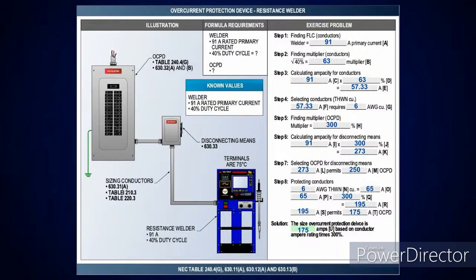So now I've already said, based on 630.32(A), I can take it at 300%. So I'll take the 91 amps for the welder at 300%, which gives me 273 amps. It says that the rating or setting cannot exceed it, so I'm going to drop down, which is a 250 amp. Now, let's see what the difference is here. I had a number 6, 65 amps, take it at 300%, gives me 195 amps. I drop down to 175. That's quite a bit of difference there, from 175 to a 250 amp overcurrent device.